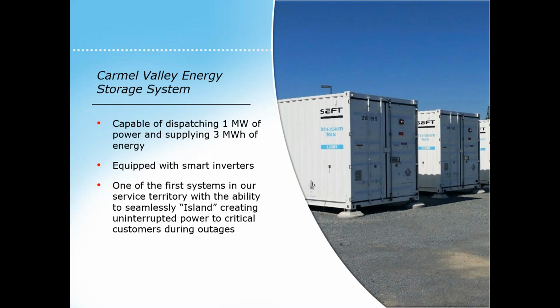What this battery system does is, in the event of an outage, it seamlessly takes over the load of the gymnasium, and that customer won't see any detectable interruption of power. That's what we call seamlessly islanding — essentially creating a smaller version of the grid that's just the energy storage system and the critical customer, the gymnasium.